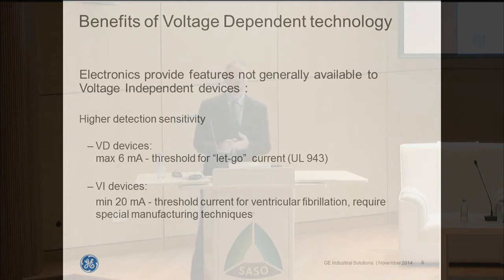So with respect to some of the specifics on the voltage-dependent devices, they, relative to the voltage-independent devices, will have a trip threshold that's a maximum of 6 milliamps. And I have a chart to help you understand what that means later in the presentation. But that's what we typically call a let-go current. So the human body, when it's faced with 6 milliamps of current flowing through it, a person, if they're holding on to the wire, for example, can still let go of the wire when 6 milliamps is flowing through you. The voltage-independent devices will tend to have a 20 milliamp threshold, and this is a threshold that will cause the body more physical pain and tends to be close to a limit where ventricular fibrillation will happen. And so it's much closer to causing the body much more harm than the 6 milliamp level.